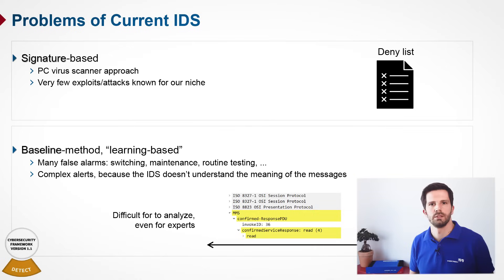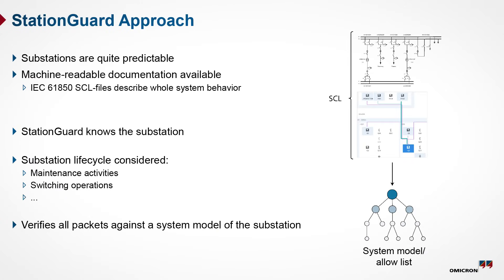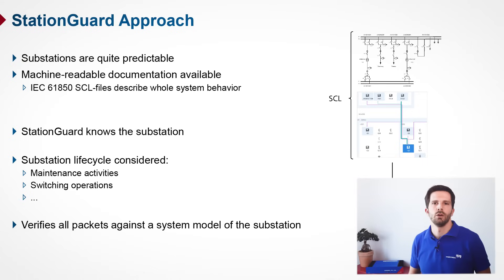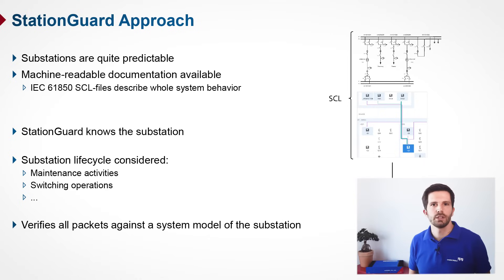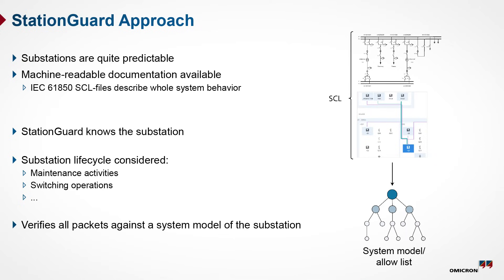With Station Guard we used a different approach, leveraging the fact that substations and the power grid in general are quite predictable. With substations according to IEC 61850, we have the advantage of machine-readable documentation of the whole substation and its communication, in so-called SCL files. The intrusion detection system Station Guard reads these files, learns the behavior of the substation, and compares each and every packet in the communication against this system model, precisely detecting what is right and wrong in the communication.